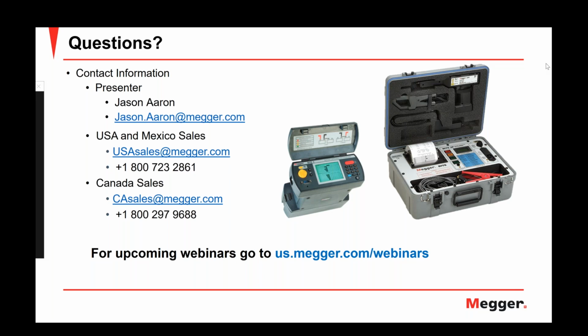All right, thank you. Jason, what are permissible limit values of strap resistance? There are some permissible limits for strap resistances. As we mentioned in the presentation, your strap resistance values are a comparison value, and it is something that we have to keep an eye on to make sure that we have good integrity of the battery string.